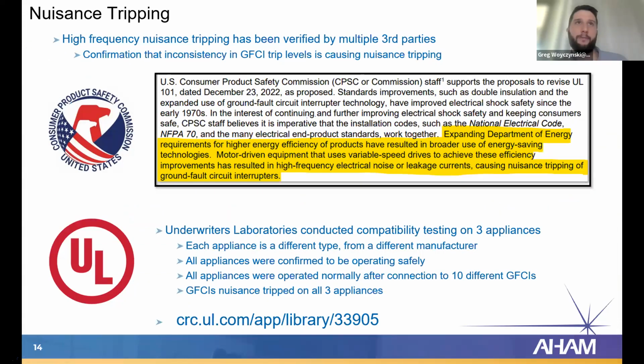And you don't have to take my word for it. There's multiple third parties that have also investigated this and come to the same conclusion. Inconsistency in GFCI trip levels causes nuisance tripping. CPSC, the Product Safety Commission from our federal government, has looked into this and issued a public letter noting that electrical noise causes nuisance tripping of ground fault circuit interrupters. Underwriters Laboratories has conducted a compatibility study without any funding from the appliance industry. This was self-funded by UL.